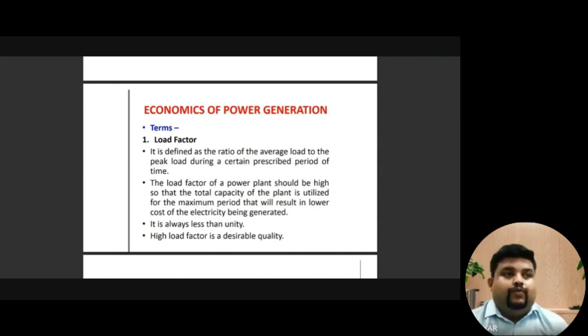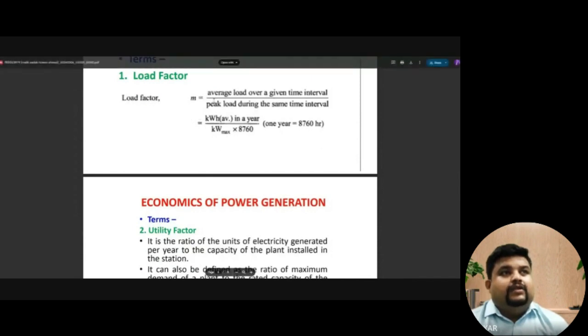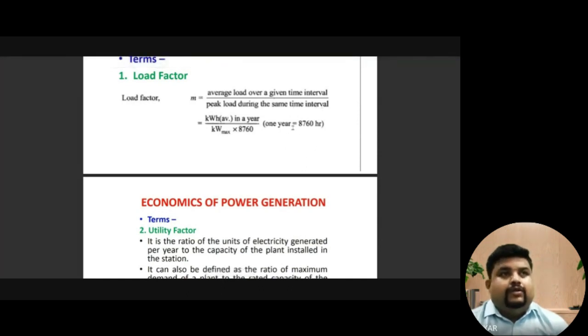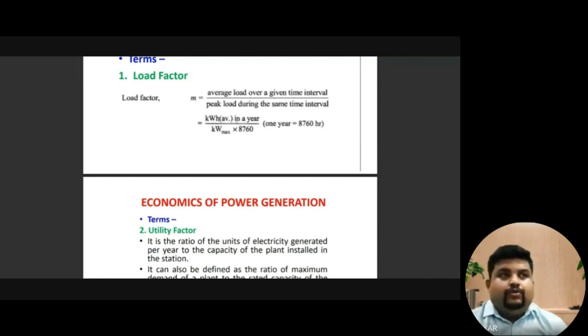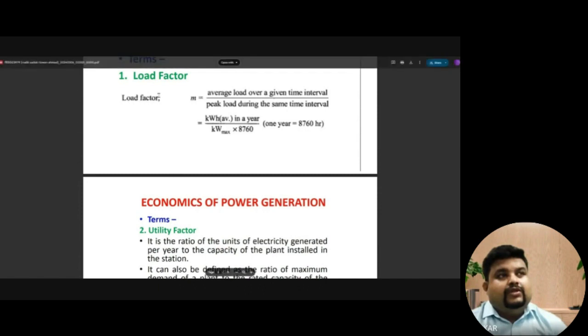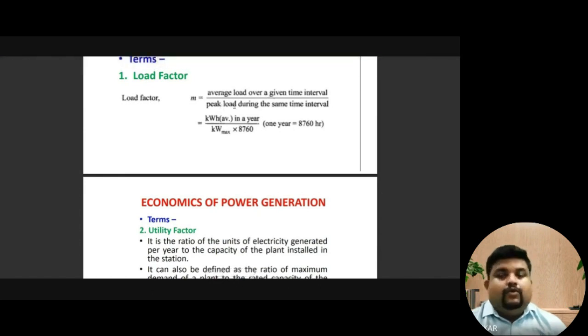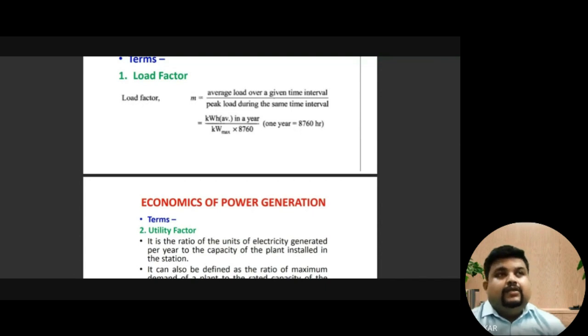The load factor is calculated as average load over a given time interval divided by peak load during the same time interval. One year is converted into 8760 hours. The maximum demand is in kilowatts, multiplied by hours, giving kilowatt-hours (KWH). When we have these two values — average load for the time period of one year and peak load, which is the maximum capacity of the plant — we can calculate the load factor.